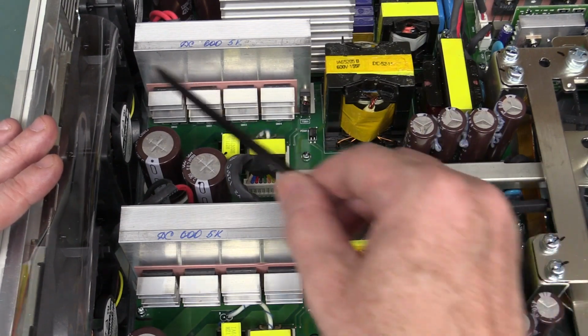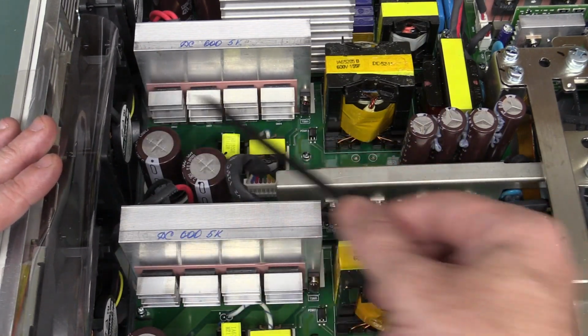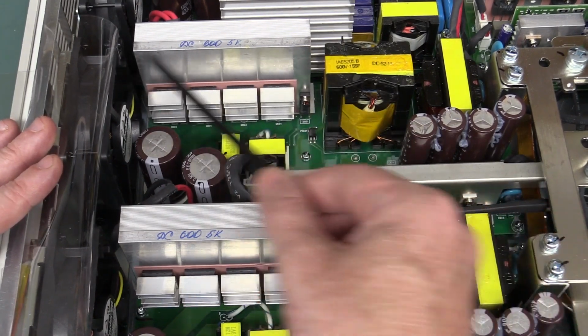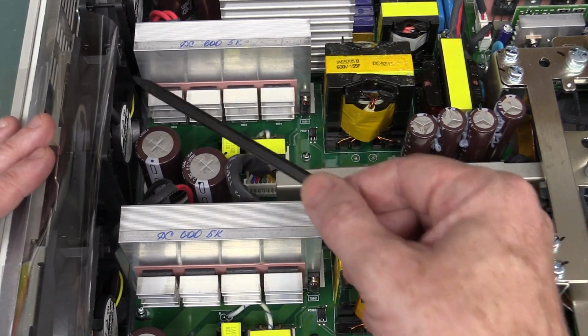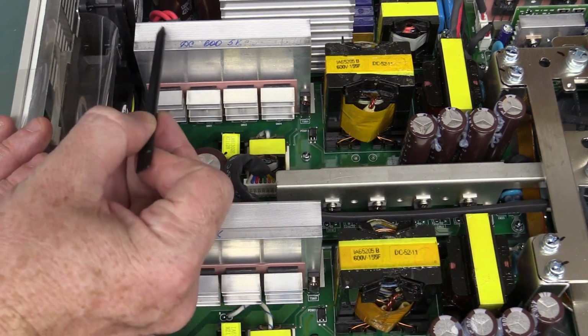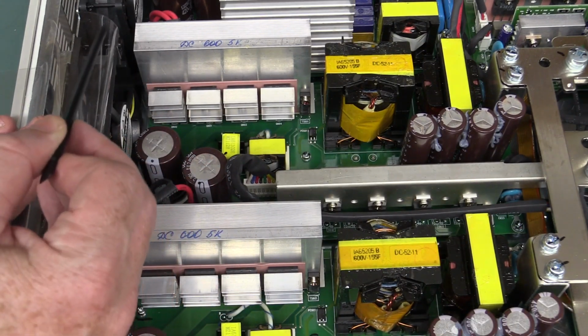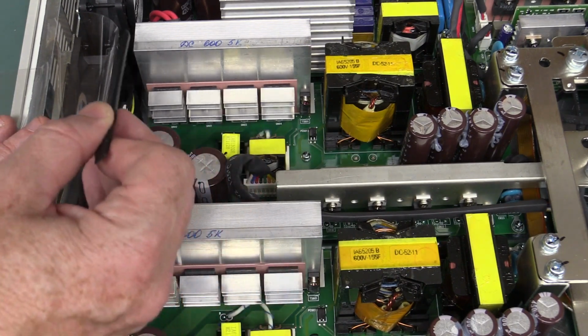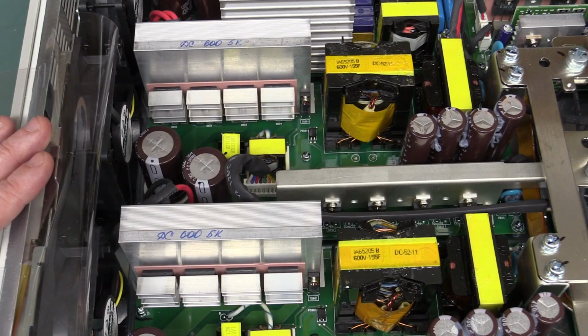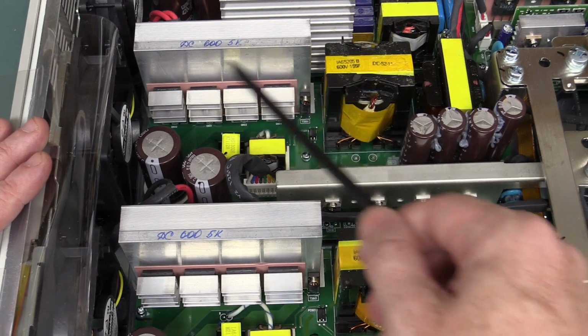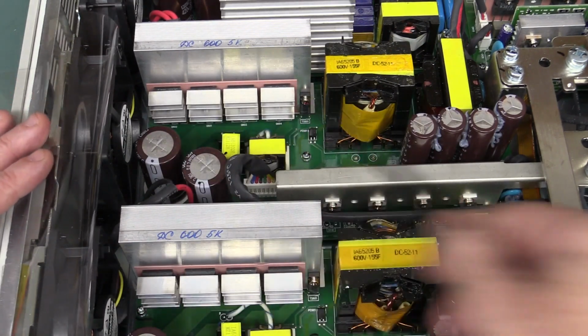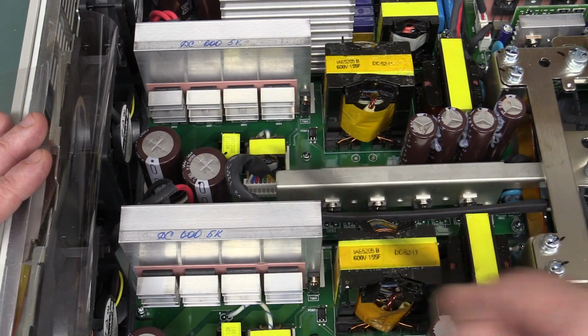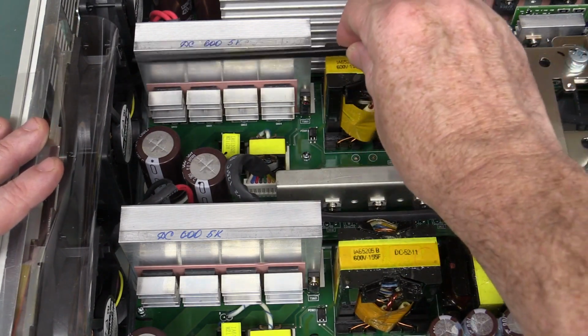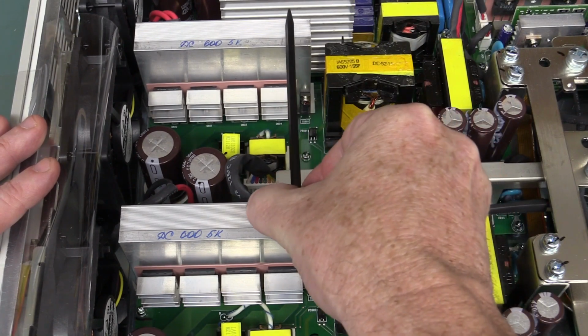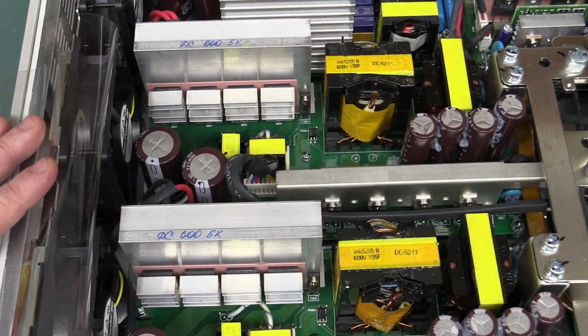This is a pretty efficient design, but as you can see, they've got the fans right here, driving the air directly over these. The heat sinks are oriented in the correct orientation, except it would have been nice to put this in the path of the fan here instead of just slightly outside the path of it. Would have been nice to get that air going over the fins, but they've done their homework, they've done their testing, and that's adequate. So that's small, and so yeah, air being sucked in the front and pushed right out the back directly across all of these. Would have been a real faux pas if they mounted the heatsink in that orientation and just blocked all the air. That's a trap for young players, that one.